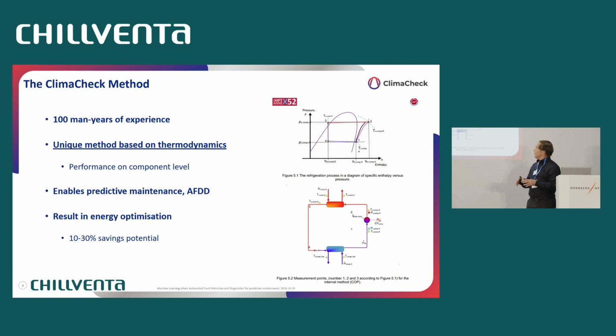And for those that think that we need a flow meter, there is a flow meter in every refrigeration process. If you look at the compressor and believe in the energy laws, if I put energy into the compressor, it will have to come out. Otherwise, it will melt. It comes out in two ways. One is enthalpy increase of the refrigerant, and then a small part is a heat loss from the shell. And that heat loss is small, and it doesn't change a lot unless you have active cooling of the compressor. If you have active cooling, we need to model that active cooling. But that is a few percent of the market.